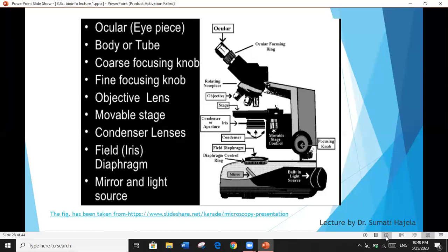Now, objective lens system is located at the lower end of the tube facing the object. It is attached to the revolving nose piece. It is very important as it affects the quantity and quality of image seen by the observer. The functions of the objective lens system are resolution and magnification. Their magnification may be 10x, 40x, 60x, or 100x, out of which 100x objective lens is called oil immersion objective lens. Most commonly used medium for immersion is cedar wood oil with refractive index of 1.5, which prevents dispersion of light rays. The lens must be dipped properly and completely in the oil for accurate image formation.